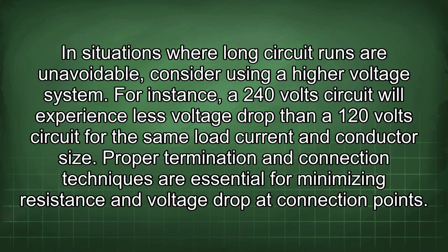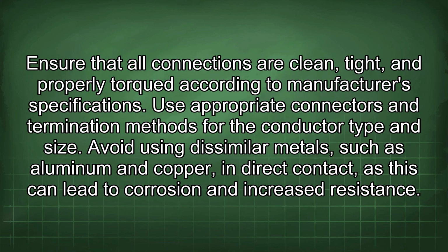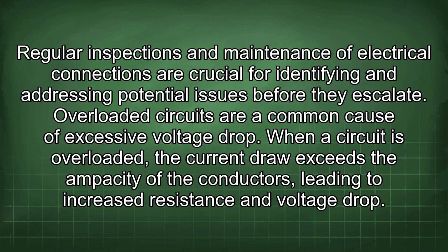Proper termination and connection techniques are essential for minimizing resistance and voltage drop at connection points. Ensure that all connections are clean, tight, and properly torqued according to manufacturer's specifications. Use appropriate connectors and termination methods for the conductor type and size. Avoid using dissimilar metals, such as aluminum and copper, in direct contact, as this can lead to corrosion and increased resistance. Regular inspections and maintenance of electrical connections are crucial for identifying and addressing potential issues before they escalate.